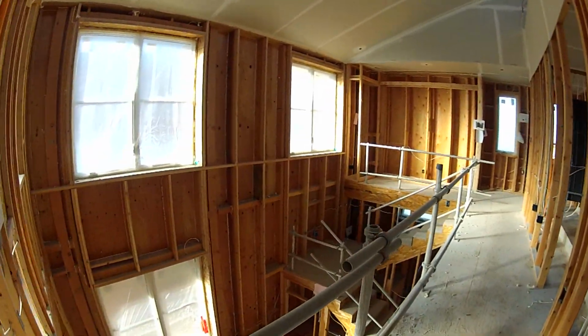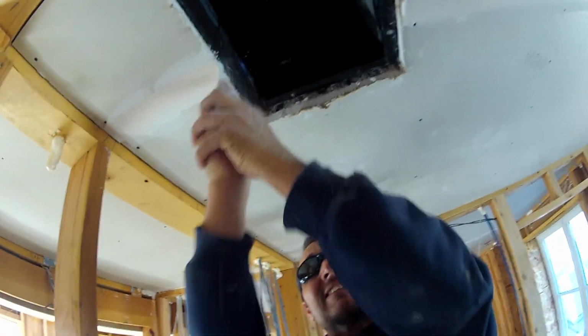In most residential constructions, ductwork leaks significantly. In all of the systems I've tested, I've never found a ductwork system that leaks by less than 10%, and I've found plenty that leak by more than 40 or 50%.